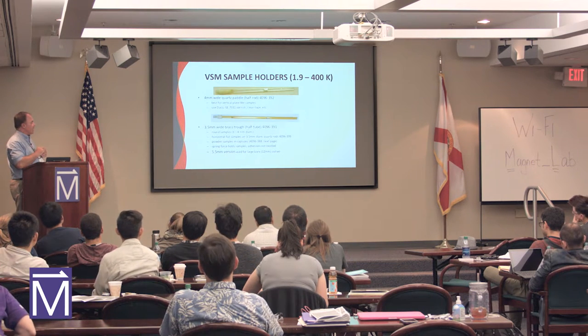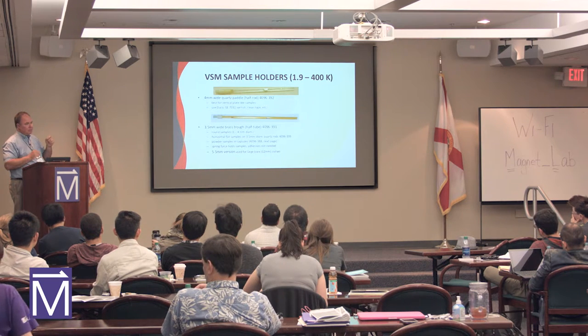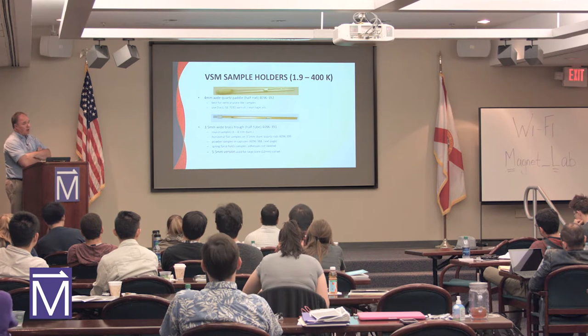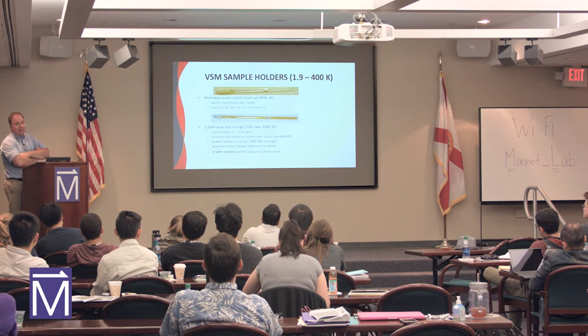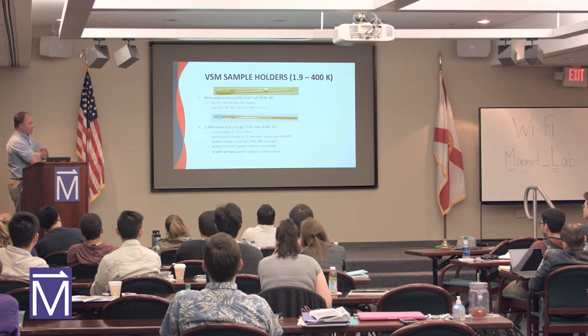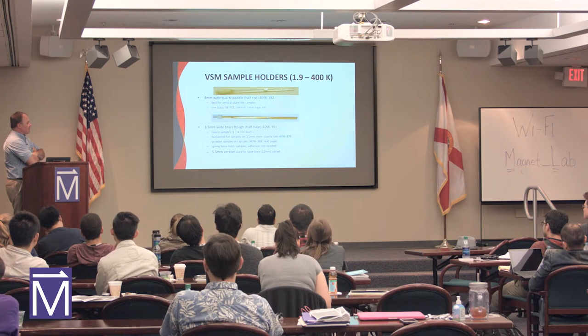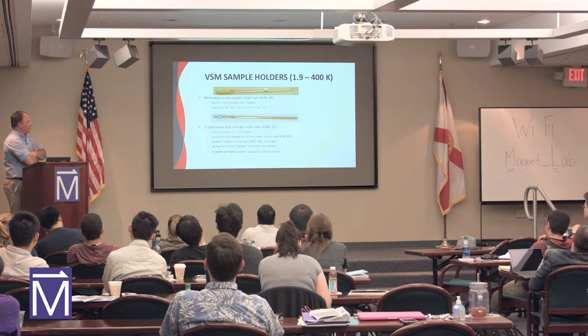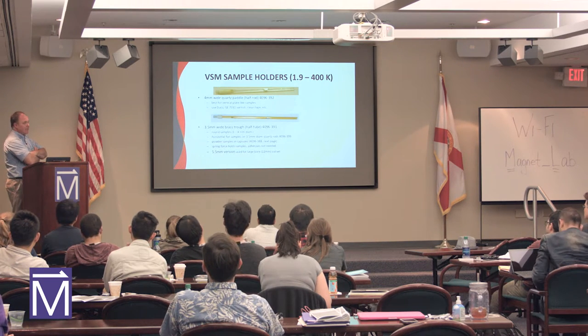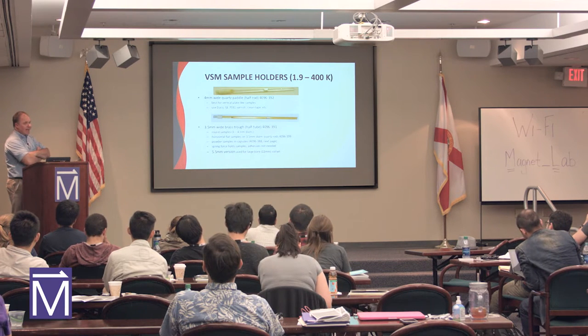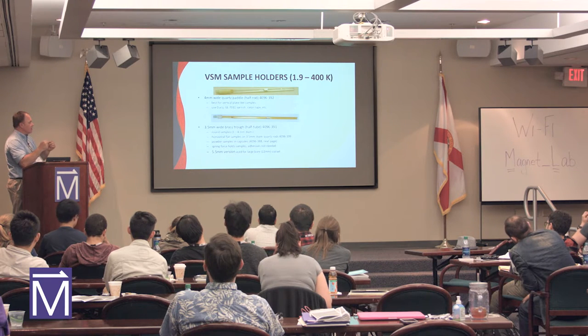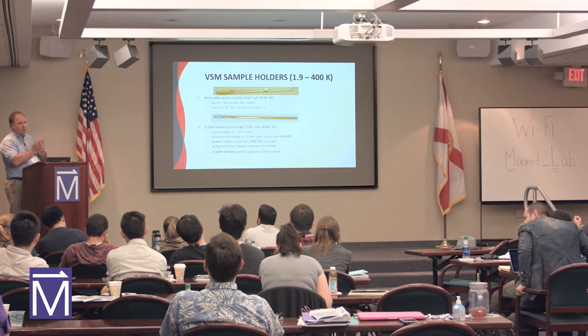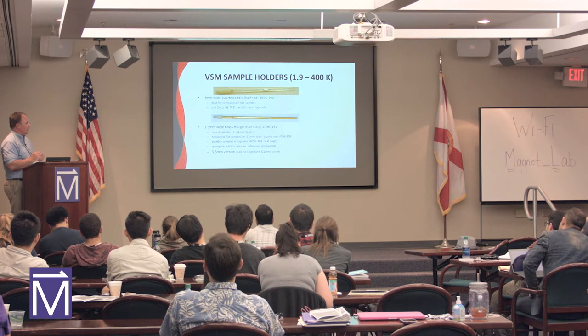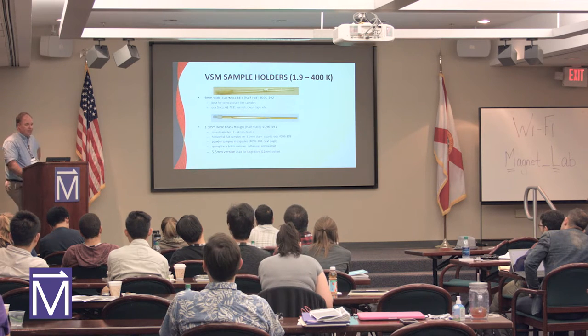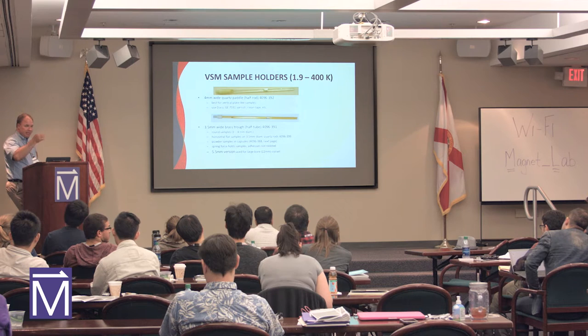VSM sample holders, you'll see this in the lab. We've got a quartz paddle. Mount your sample to the quartz paddle with some varnish, cement, some tape, Kapton type tape. We've got a little brass holder with a couple of capsules that hold the sample in place. There's also a little powder holder where you can put powder inside and hold the powder inside the part of this vessel and clamp it together. So the brass tube sort of holds it mechanically in place. And then we've got a little larger version of the same brass tube that fits into the large coil set. So we've got a small and a large, 6 millimeter and a 12 millimeter diameter coil set, so the pickup coil diameter.